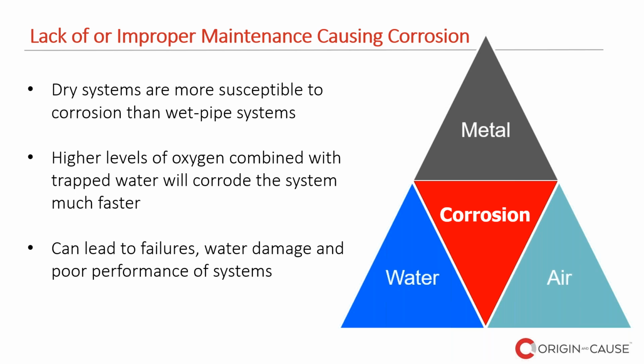If corrosion is not inspected, detected, and properly dealt with, it can lead to failures and obviously damages from it. When it comes to what is required, the NFPA 25 clearly identifies what needs to be done. So there is no back and forth as to what the contractor had to do. It is all very clearly specified, and if not done, then we see the results.